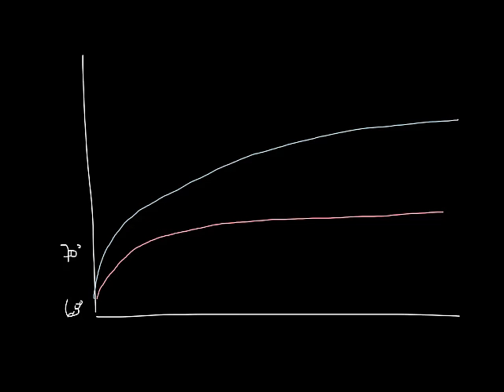We run tests with perimeter diffusers set up in the 50-50 compromise position I discussed at the beginning of the podcast and compared how quickly a room got up to set point during heating. What we found is this: if you draw this and temperatures go up here and time goes across the bottom, if you started at 68 degrees, after an hour the 50-50 compromise setup was only at about 70 degrees, whereas the auto changeover setup was at 74 degrees after an hour. The difference between these two lines is basically the energy savings of having the air go into the correct position all the time.